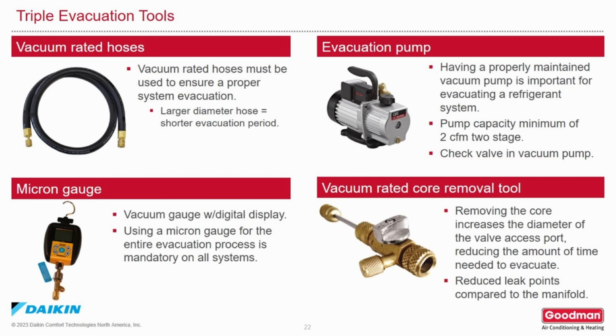The tools needed to perform a triple evacuation are as follows. Vacuum-rated hoses. The larger the diameter of the hose, the shorter the evacuation time. The red, yellow, and blue hoses that come with a manifold gauge set are typically not vacuum-rated. When possible, try to avoid using a manifold set for an evacuation.